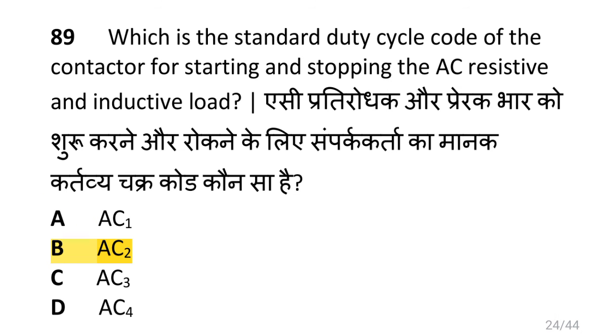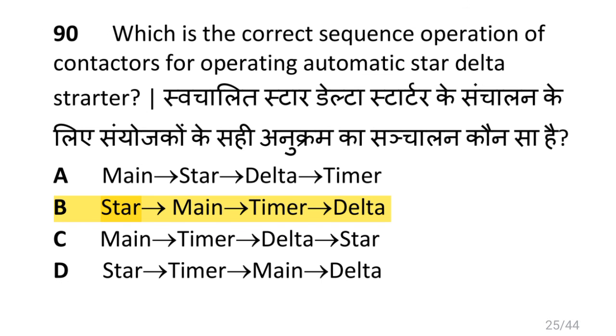Which is the standard duty cycle code of the contactor for starting and stopping of AC resistive and inductive load? i.e. AC2. Which is the correct sequence of operation of a contactor for operating automatic star delta starter? i.e. star, main, timer, then delta.